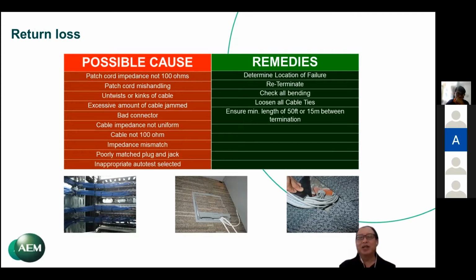Return loss is also another secondary common problem that we see on site. Return loss is usually caused by components. So sometimes we encourage you to use one brand. If you use CommScope, make sure your connectors, your cables, your jack, patch cord all come from the same brand. The reason behind it is the impedance, which is measured in ohms.